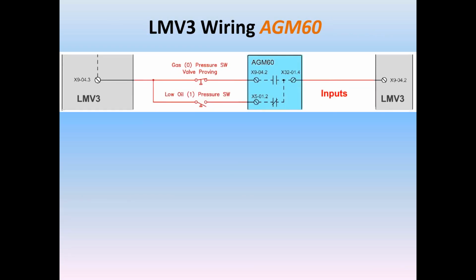The AGM60. The AGM60 is the dual fuel module. So you have an LMV36. In this case, 942 would be output to energize an input device. That would be an input going in there. So you would take power from 943, and then on fuel 0, in this particular case, we'd have a valve proving switch. That would go through the AGM60 and get presented to 942 as an input. And when we switch the AGM60 over to fuel 1, now we're on oil, and now we have a low oil pressure switch coming into the AGM, and the LMV3 on 942 sees the condition of the low pressure switch.